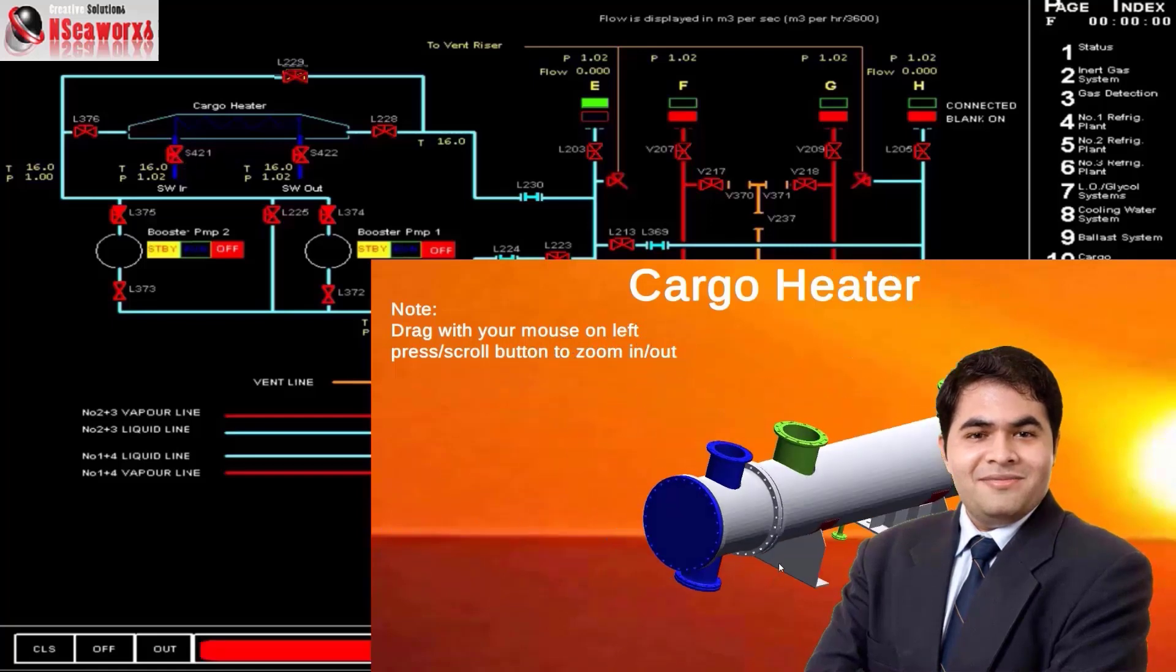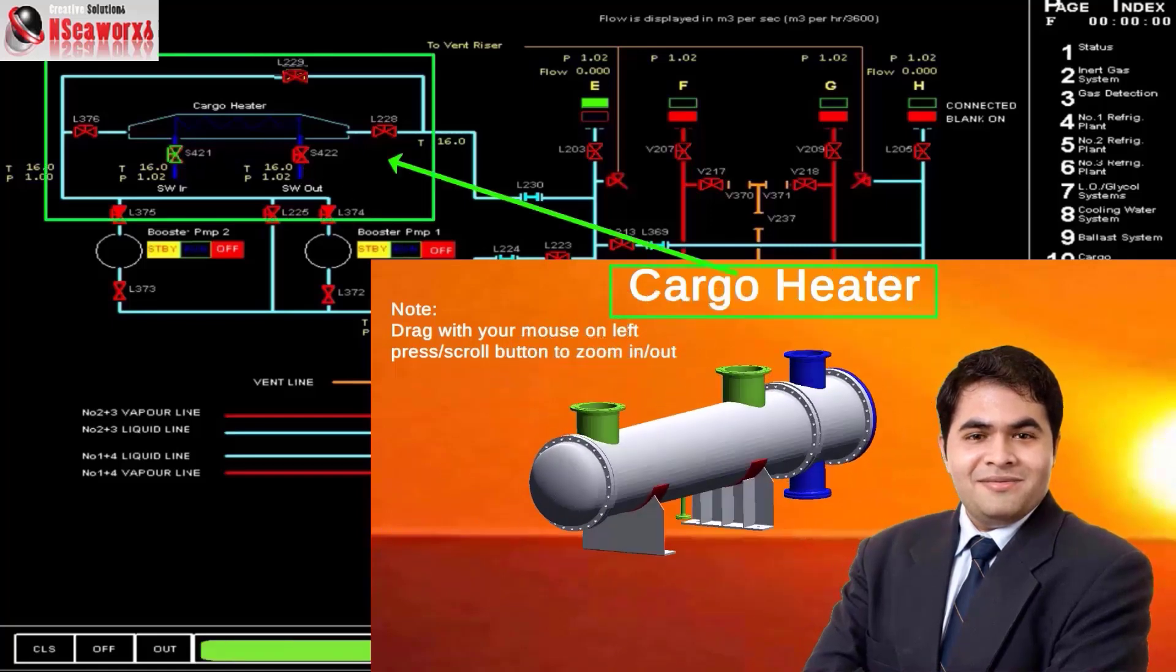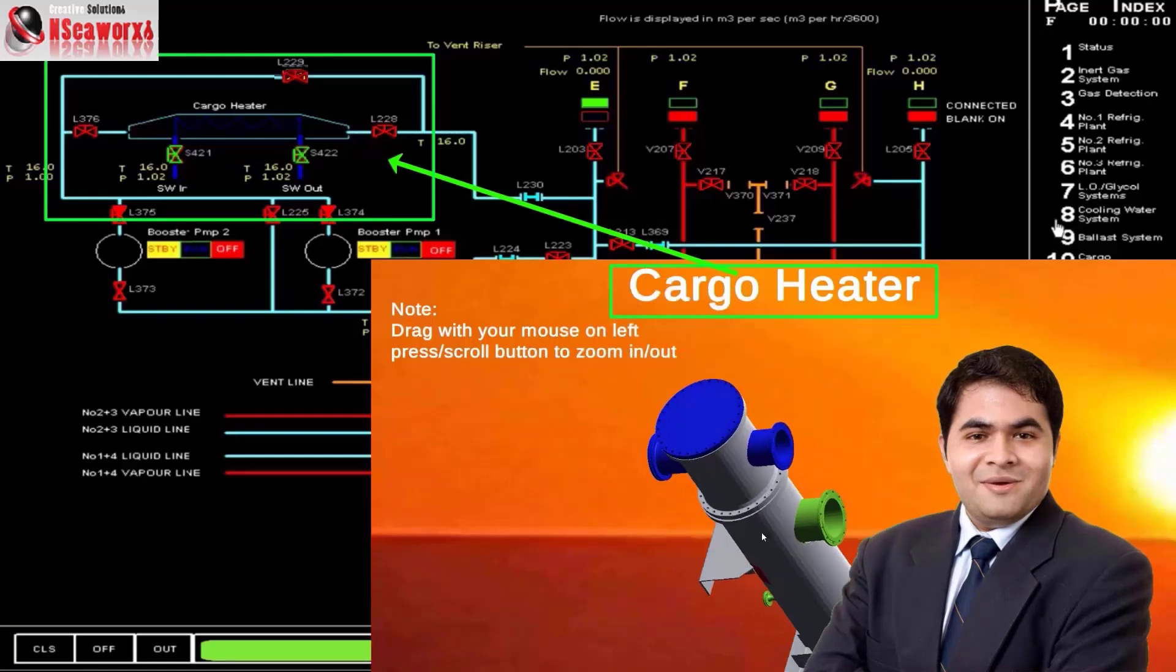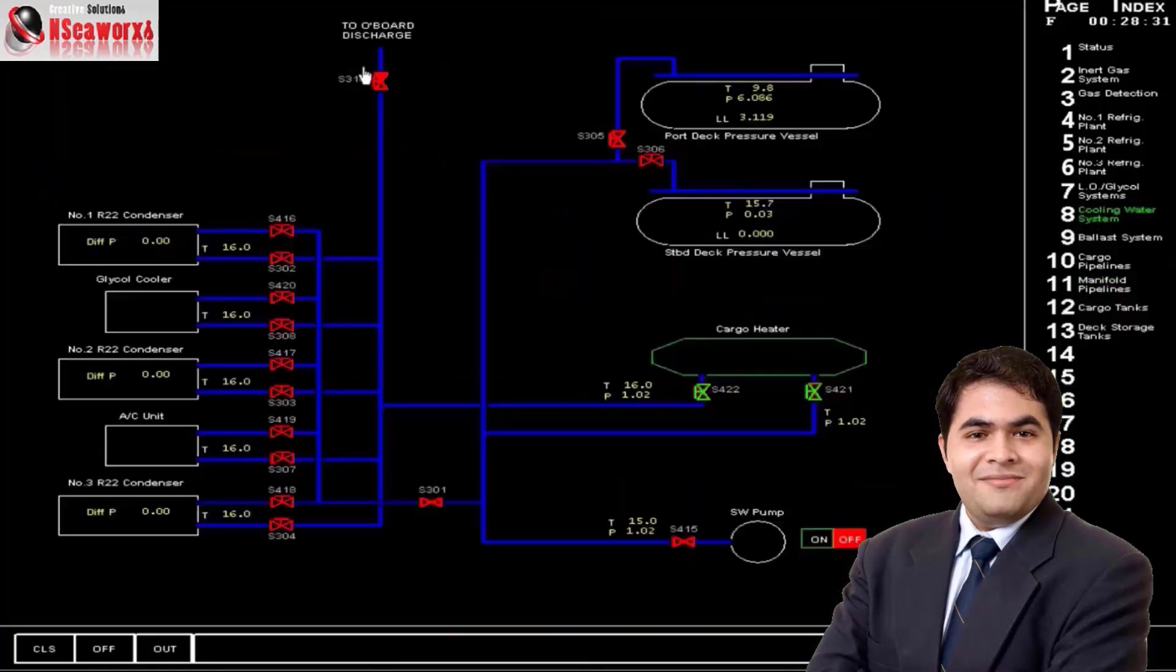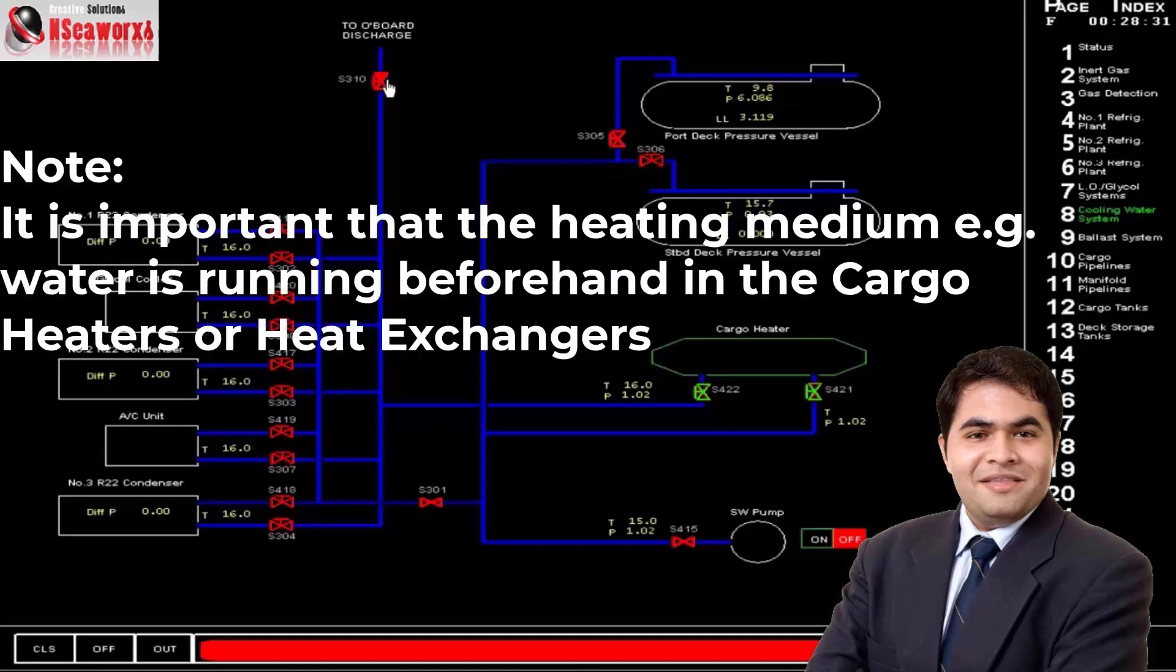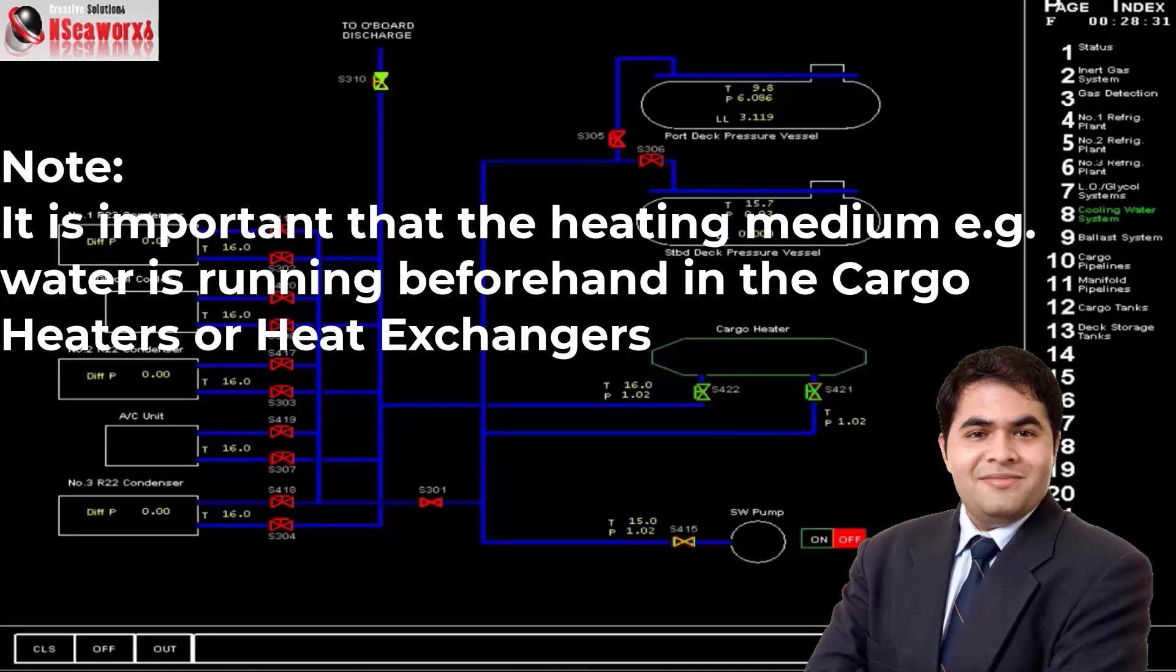Then we can open the supply of seawater. We can also go to the cooling water system. As you can see, it's open. And make sure that the overboard discharge valve is open as well, and the supply of seawater pump. Now, we can start the pump.